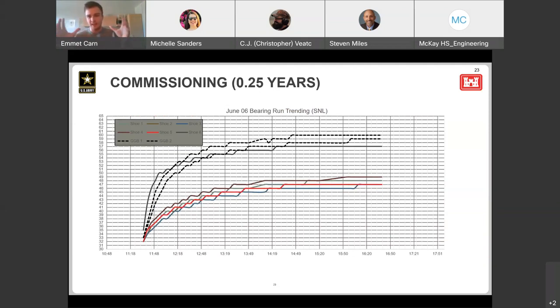If those bearings are getting really hot, we know there's a lot of vibration in the unit and something going on that we need to shut down for. So during commissioning, we look closely at bearing temperatures to make sure they stabilize over time and don't overheat, because that can tell us there are issues with how we've reassembled the unit.